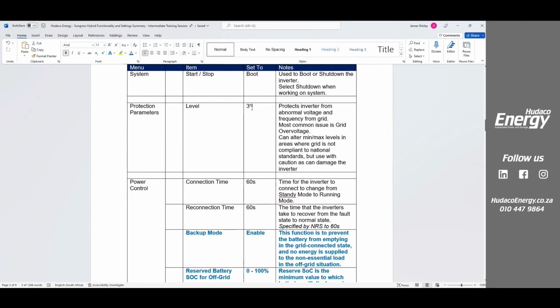It allows us, even though the national standard says voltage can go up to 253, in other words, range from 195 to 253, it allows us to ride through as high as 276 volts for a short amount of time if there's a spike in the voltage, which during load shedding is happening quite often as they bring transformers up and down across the city. We're seeing voltage spikes happening.